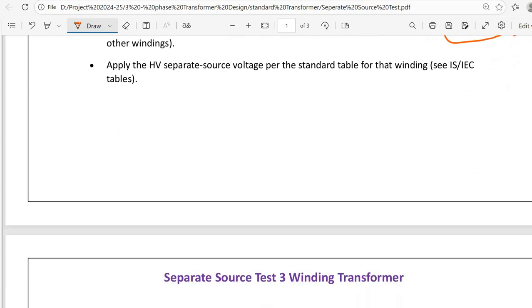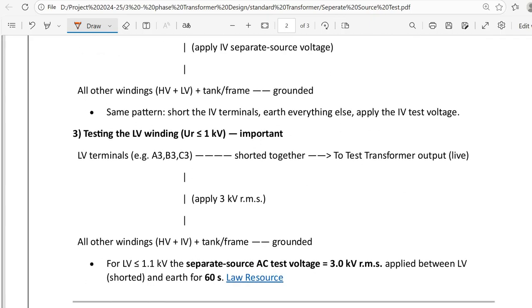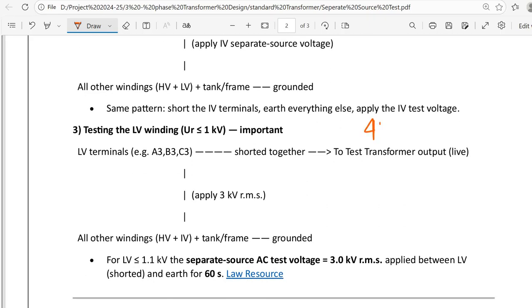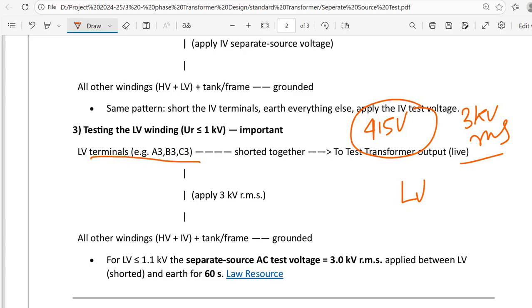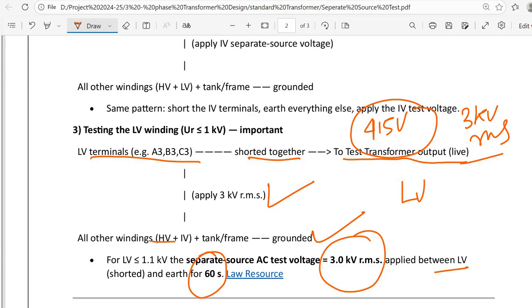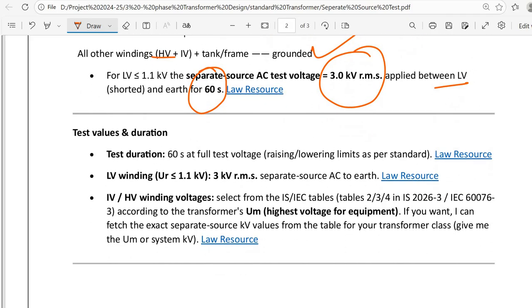Now if you want to test an LV winding, and the LV winding is 415 volt, it should be tested at 3 kV RMS. All LV windings are shorted together and 3 kV is applied. LV terminals R, Y, B are shorted together and connected to the test transformer output live, and 3 kV RMS is applied. All other windings, HV, and the tank and core are grounded. For LV less than or equal to 1.1 kV, the separate source test voltage is 3 kV applied between LV and earth, held for 60 seconds, which means 1 minute. So this is the separate source test.